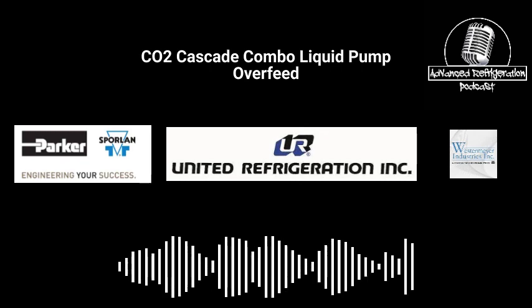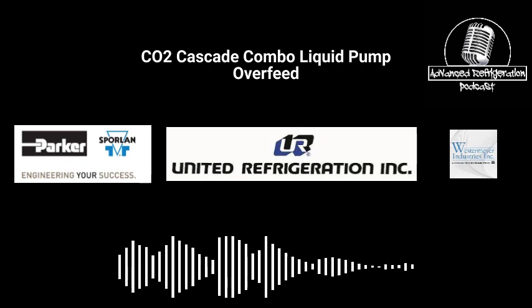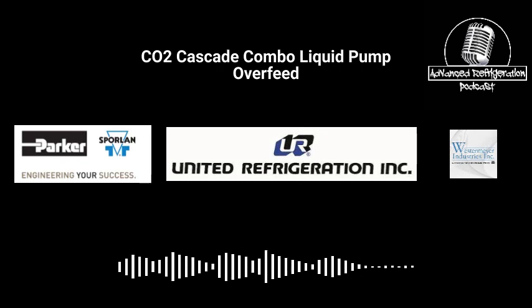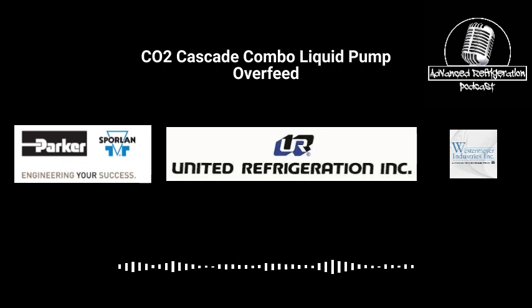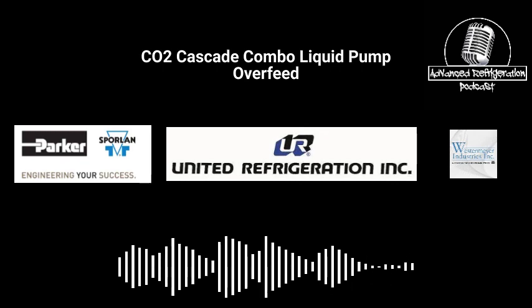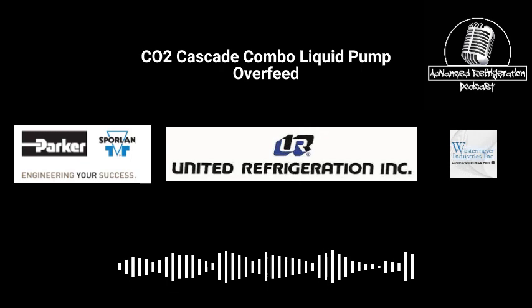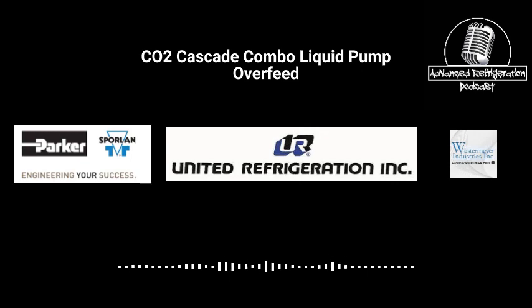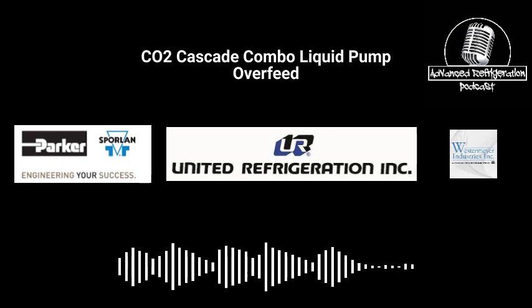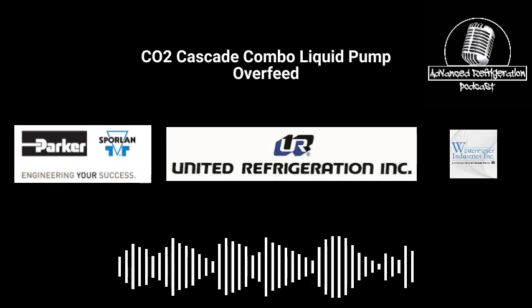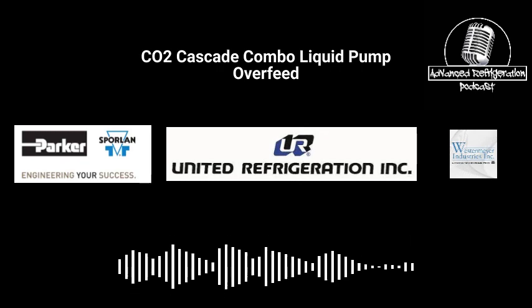Yeah, absolutely. On these racks, in parallel with the vapor liquid separator, as they call it, is a refrigerant tree, basically a pipe that goes up from the bottom to the top of the vapor liquid separator. It has markings on there for 5, 15, 25, 50, 80, and 90. Typically, you want to get these charged up to 80%. That doesn't mean 80% running. That basically means you shut down the master defrost switch, where everything will start pumping out. Theoretically, the system should get up to about 80% and shut off. That's where it really wants you.